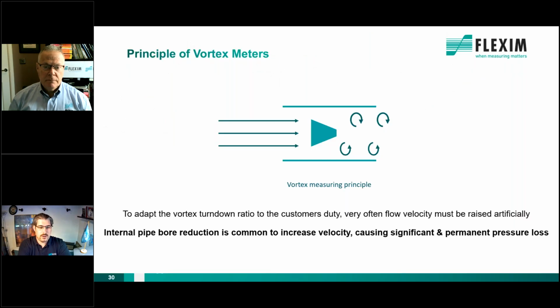To give you a better idea about the inline principles, here's one. This is the vortex meter, basically the most common one used for steam nowadays. The thing is here, by the principle, you have your measuring pipe, and you have your kind of obstacle in the pipe that creates those vortices. And the higher the flow velocity of your steam, the more vortices you will generate. So the frequency of vortices will increase. And basically you can measure the number of vortices you have. So basically you count the number of vortices inside your pipe, and so you get to the actual steam flow. The problem is, to create those vortices, you need a certain amount of flow velocity. And most of the time you do not have it.